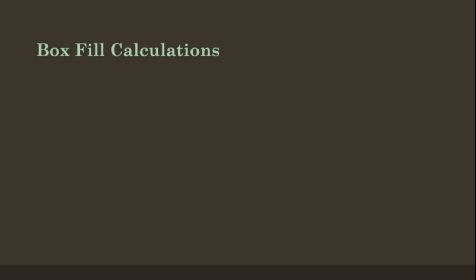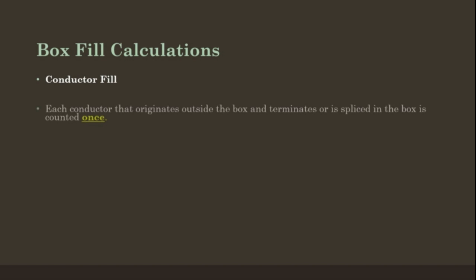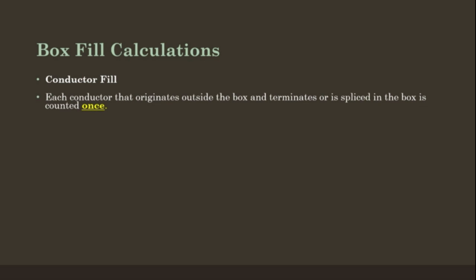Box fill calculations. Conductor fill: Each conductor that originates outside of the box and terminates or is spliced within the box is counted once.